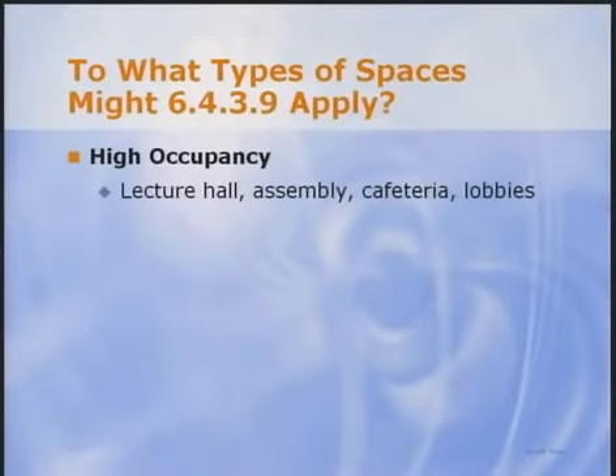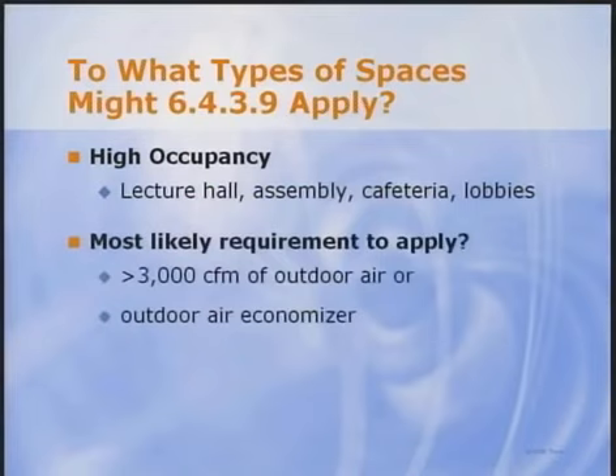Putting my engineering hat on, the high occupancy spaces that come to mind are assembly spaces, whether places of worship or an auditorium. Also spaces such as lecture halls, lobby areas, and cafeterias may meet the criterion of a high occupancy space. Then the most likely of the three other requirements are that either the system has a required ventilation rate over 3,000 CFM or an air side economizer.